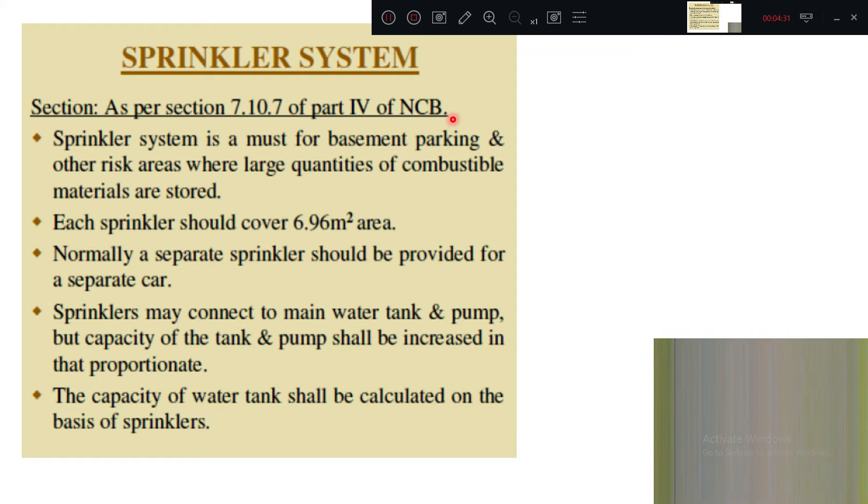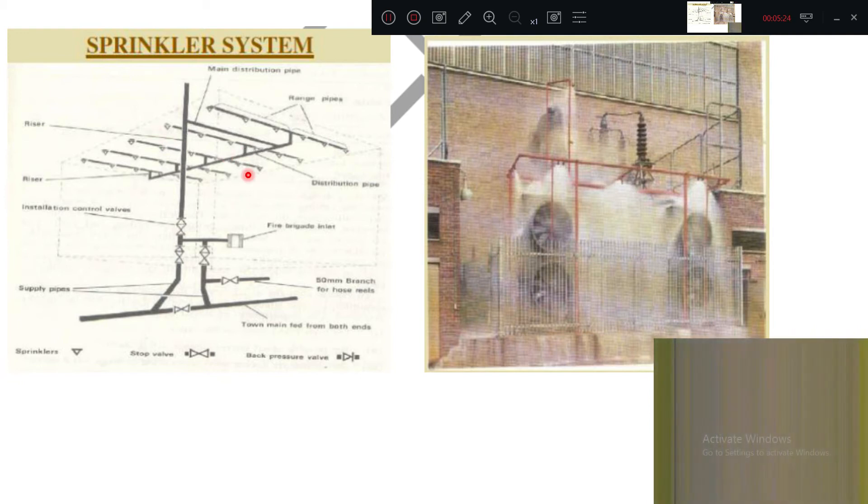The sprinkler system is explained in Part 4 of NBC. It is a must for basement parking and other risk areas where large quantities of combustible materials are stored. Each sprinkler should cover approximately 6.96 square meters. Normally a separate sprinkler should be provided for each car. Sprinklers may connect to the main water tank and pump, but the capacity of the tank and pump shall be increased proportionately for the building plus parking.